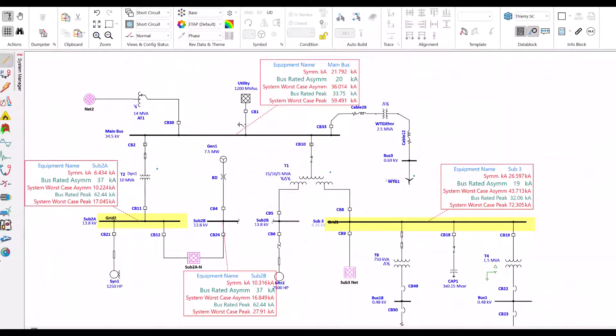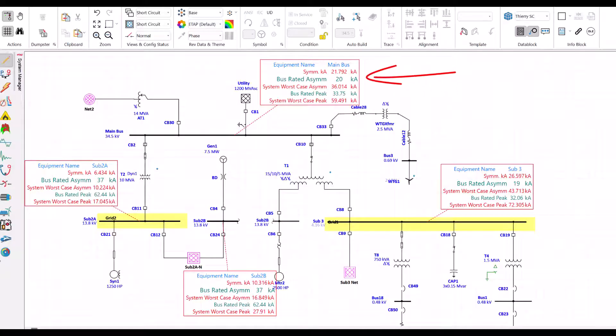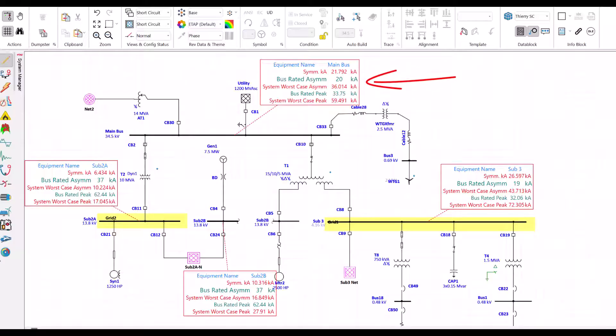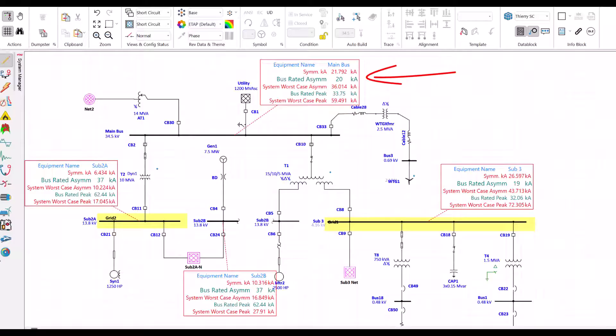Let's look at the main bus. The bus is rated for 20kA, but the system could produce 36kA. We have an issue. The bus is not adequately rated to handle the worst case fault scenario. 20kA less than 36kA - not good. Do you see the pattern? The green on top should be higher than the red on the bottom. Same for peak current. The rated peak of the equipment bus should be higher than the worst case scenario. This is what will be flagged on the report when they are not rated.